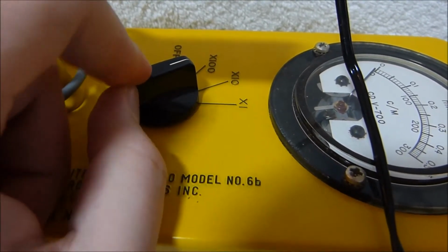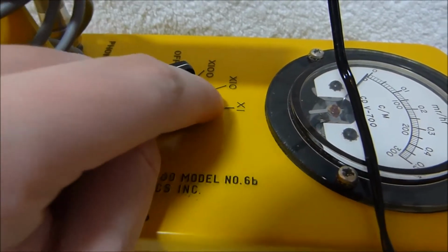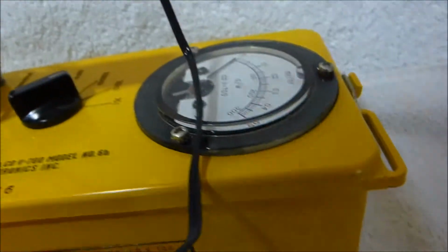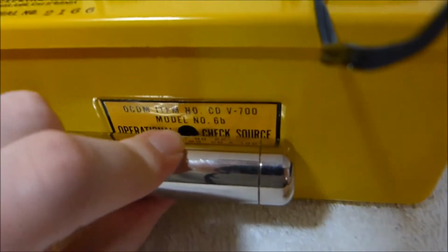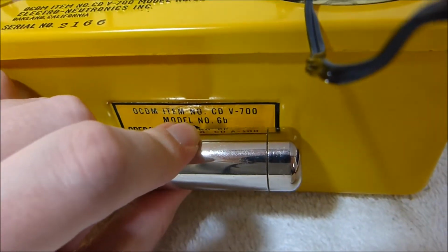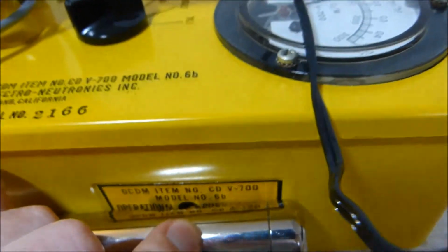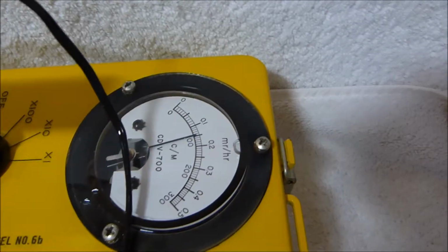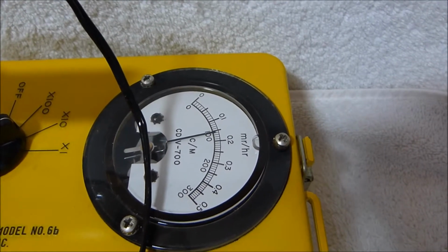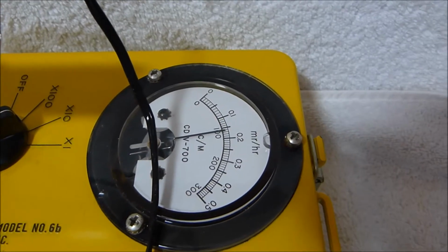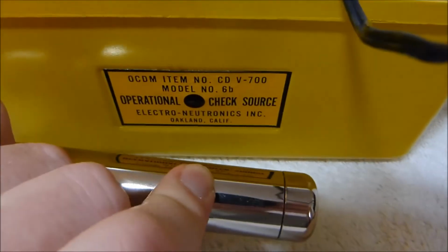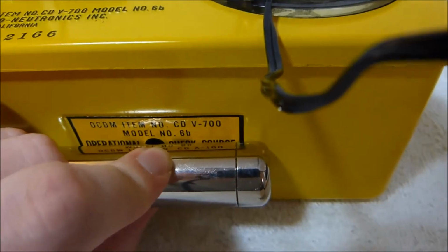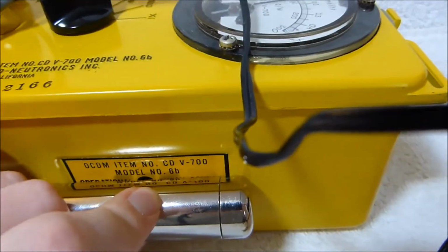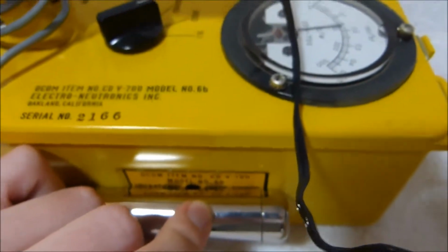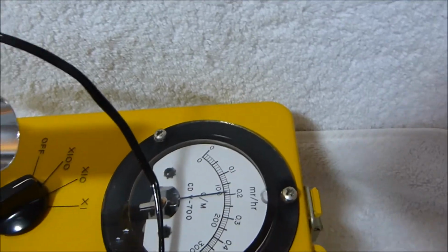Now, when testing it, the manual says to set it to the X10 range and hold the probe with the window open up to the check source, making sure that one of the bars isn't obscuring part of the check source, which is, I believe, a piece of depleted uranium. Don't peel off that sticker, by the way. The check source is right underneath it. On one of these that I had sold previously, someone had done that, so I had to seal it over with a piece of packing tape so that nothing would escape.